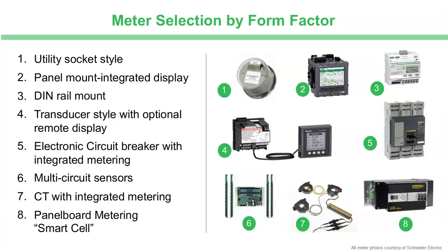So that's actually showing a breaker that has a smart trip unit, allowing it to communicate not only the protection information and the open close, but it also has the ability to do power and energy monitoring as well. Down below, we show the multi-circuit meter, which is number 6. So you see strips of current transformers, so individual circuits can be monitored. A voltage gets connected to that, and it has communications.